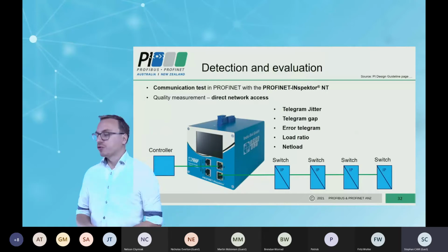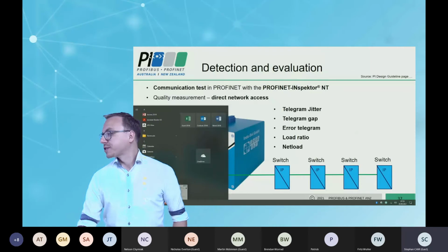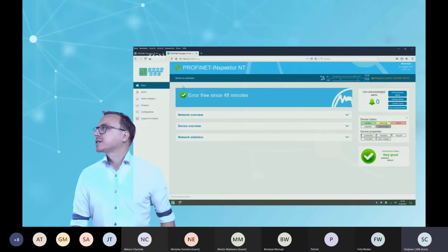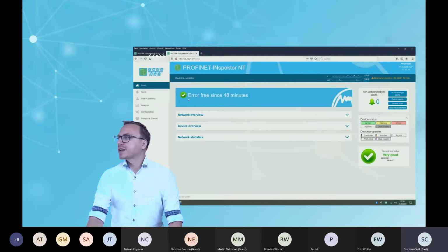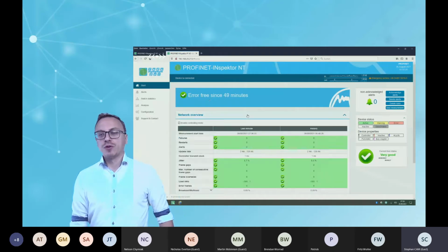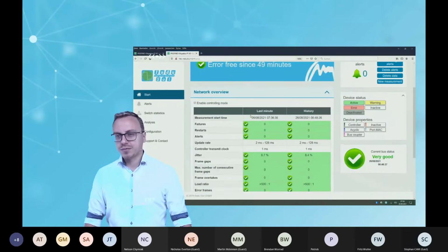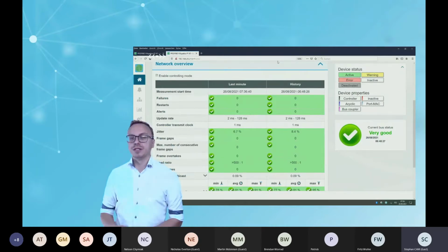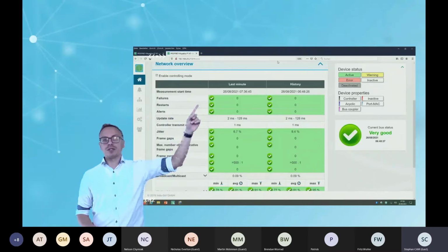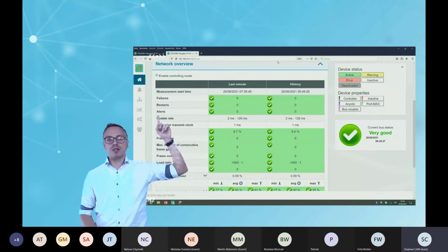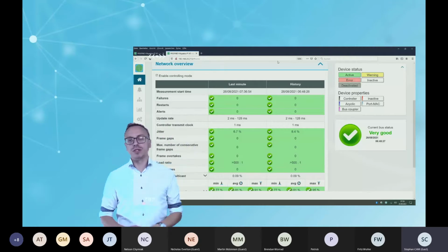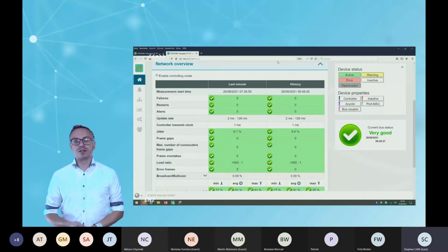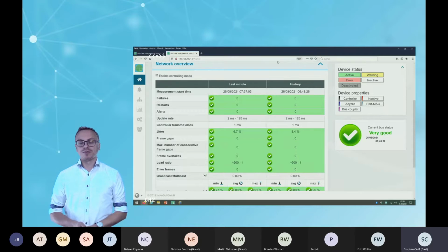How it works, I want to show you. For example, now we have here a small PROFINET installation. You can see we have the PROFINET Inspector, the measurement tool, installed, and we have some I/O devices. Let us go to the web interface of our inspector, and we see the inspector is error-free for 49 minutes. You can go to the network overview, and the inspector will show you easily all quality values in the system. You see if you have drop-offs of nodes, if you have restarts, normal diagnostic frames, PROFINET alerts. How is your update rate in your system? How is the transmission clock of your PLC? How are the jitter, frame gaps, and load ratio, all the things that you heard before. So if you get an issue now, let me try something.